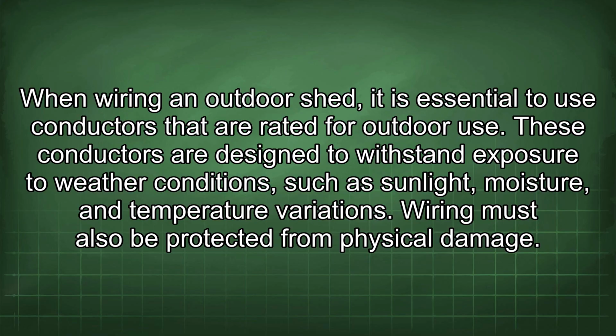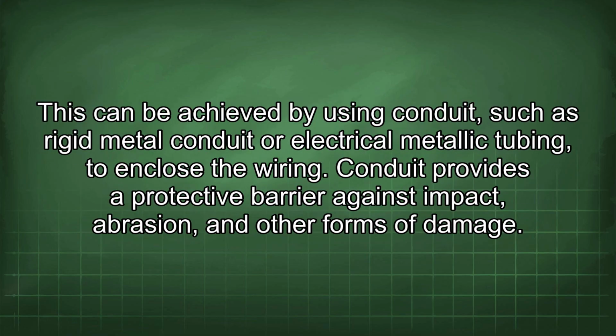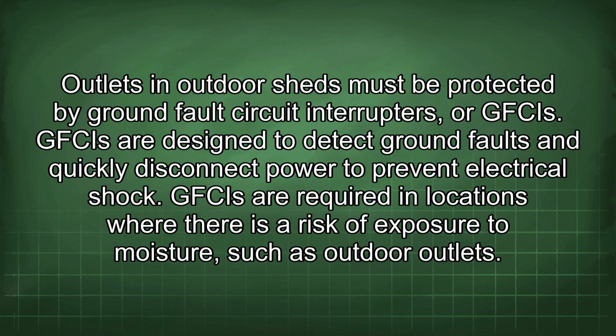Wiring must also be protected from physical damage. This can be achieved by using conduit, such as rigid metal conduit or electrical metallic tubing, to enclose the wiring. Conduit provides a protective barrier against impact, abrasion, and other forms of damage. Outlets in outdoor sheds must be protected by ground fault circuit interrupters, or GFCIs. GFCIs are designed to detect ground faults and quickly disconnect power to prevent electrical shock. GFCIs are required in locations where there is a risk of exposure to moisture, such as outdoor outlets.